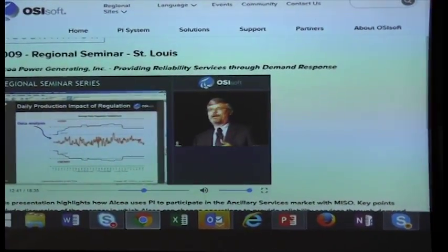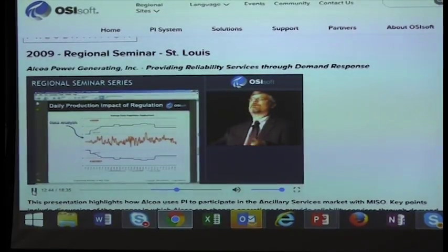I don't have to go out and champion PI. All I got to do is facilitate them as they are wanting to champion PI. Well, the smelter, they're saying, hey, we're not sure we're making enough production. We think MISO's taking us for energy far too much and dropping our load. So with Data Link, I just go in and I have a very simple spreadsheet built that I look at over the course of the day, how often was I dispatched above and below and what my incremental energy was, whether I spent more time below zero or above zero. And I put on a trend and I say, well, it looks like for the most part, you see the red line is above zero, which means MISO really takes me more for load than they do for energy.